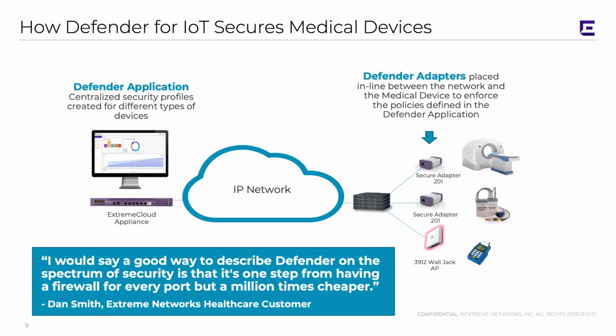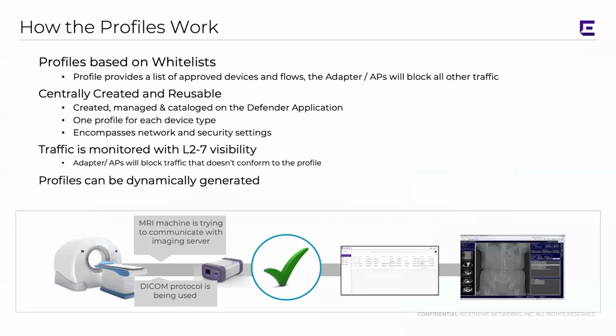So also on the right hand of the slide, there can be multiple Defender devices with each applying device-specific security policies. So this eliminates potential cross-infection of viruses or ransomware that exist on the network. Profiles are based on whitelisting and the creation of authorized communication channels. It's kind of like the least privilege approach. So the minimum necessary for the device to function. And in this, the MRI machine is using DICOM to communicate to an imaging server, and that communication is allowed. DICOM to another unlisted imaging server or any other traffic would be dropped.